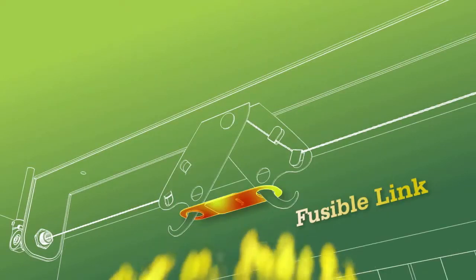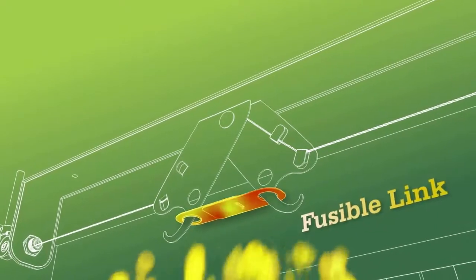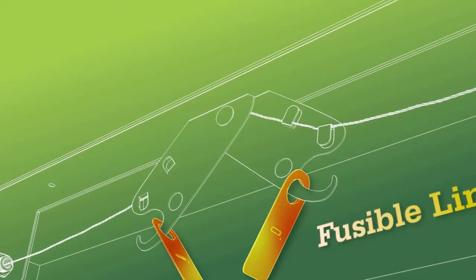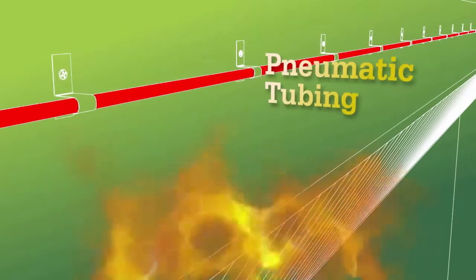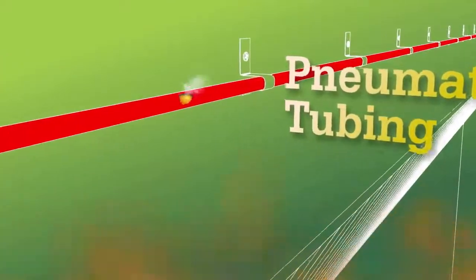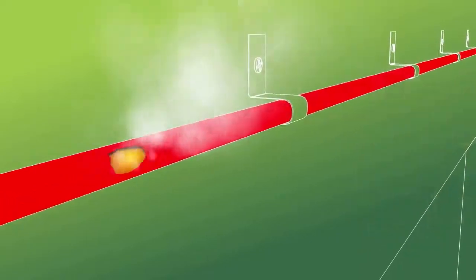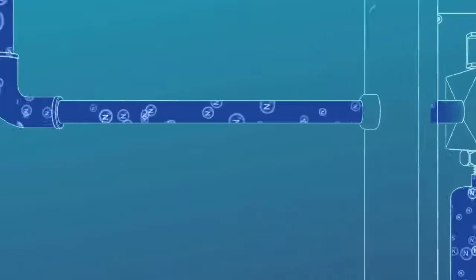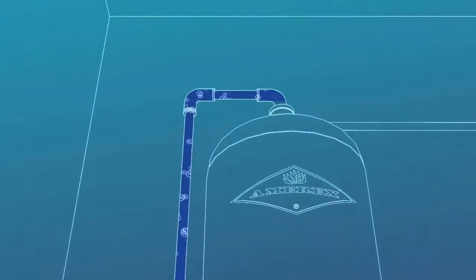But if there's no one to pull the handle, an Amerex system still provides peace of mind. The systems are automatic, either with fusible link or pneumatic fire detection. Both methods trip the system automatically when heat from a fire activates the detection device. This action punctures the nitrogen cylinder, releasing gas that opens the agent cylinders while closing the gas valve.